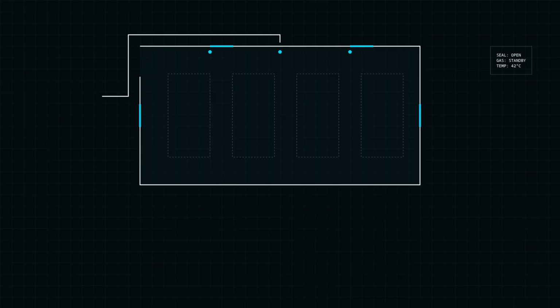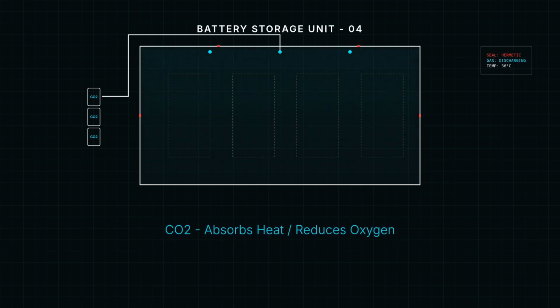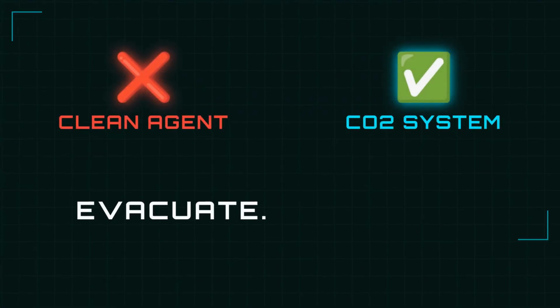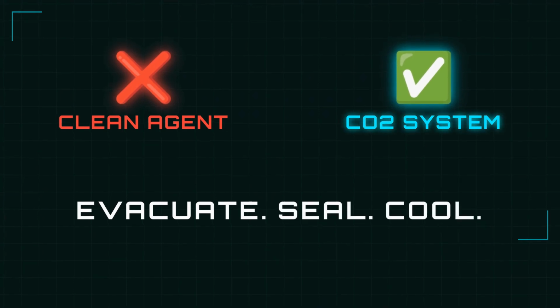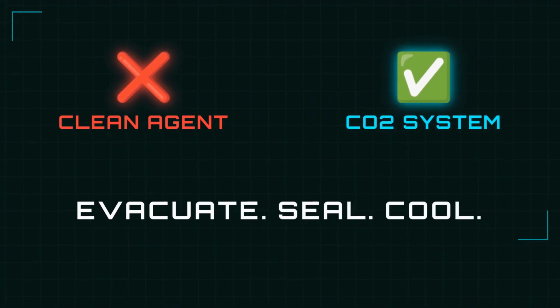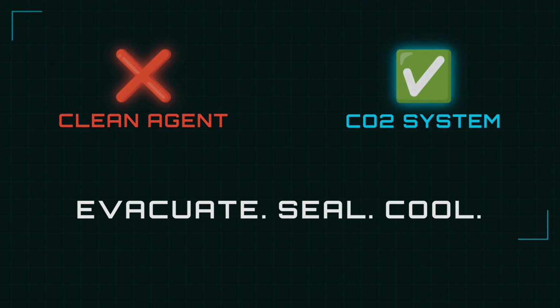Our suppression strategy is CO2 total flooding. CO2 is specified because it absorbs heat and reduces oxygen concentration. Clean agents like Novec or FM200 are simply not effective against lithium-ion thermal runaway events once they start. Clean agent cannot suppress LFP thermal runaway. Our protocol is clear. The room must be evacuated and sealed, and then flooded with CO2 to allow the system to cool down naturally and safely. It is the only way to protect the facility.